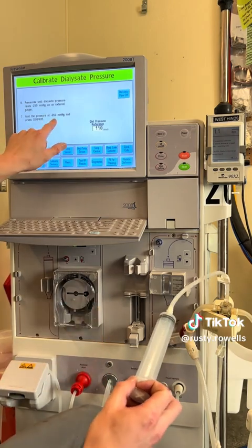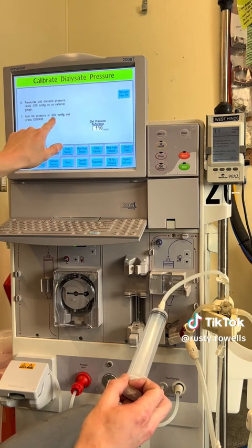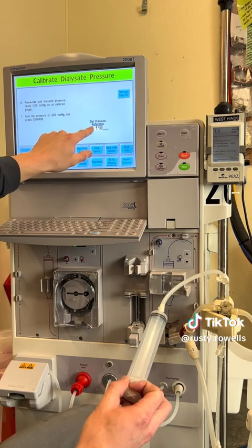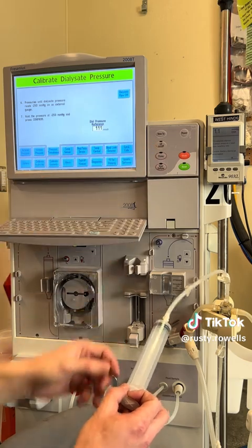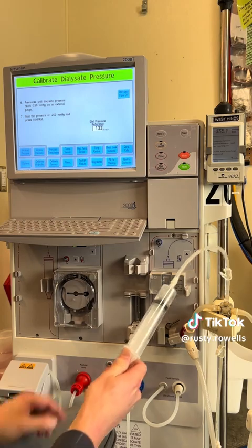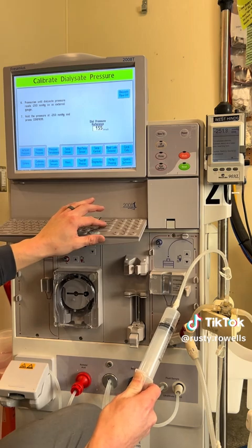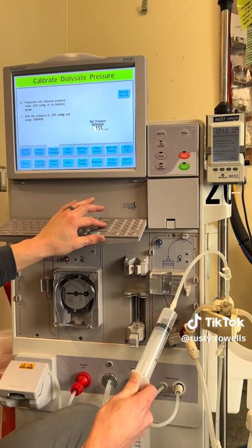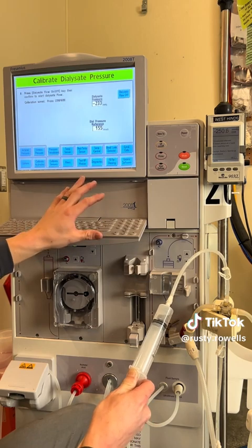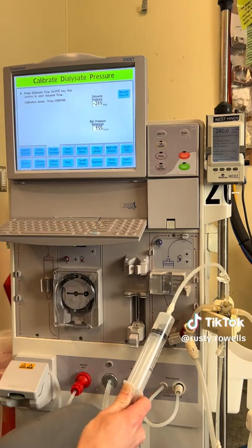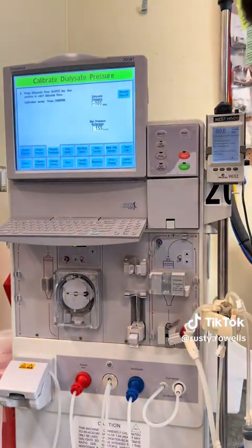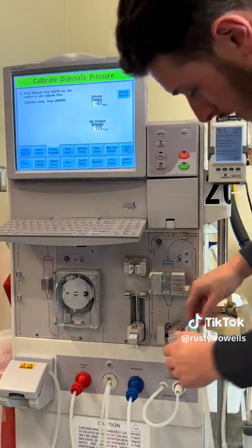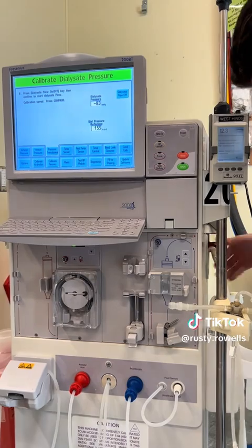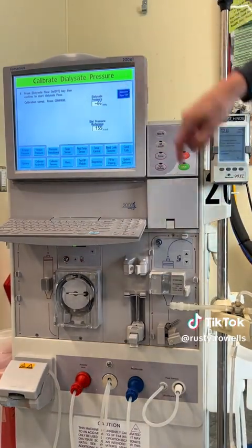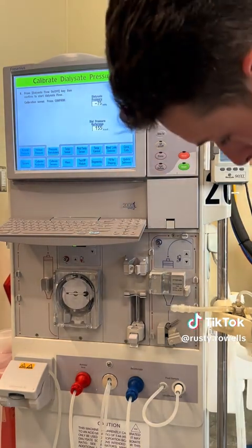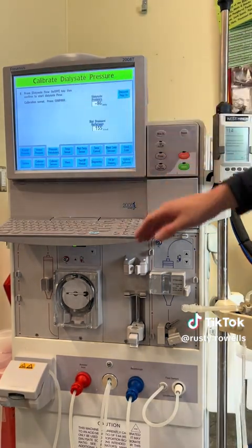Now we hit enter and we have to hold the pressure back at -250, and then hit enter to lock that in. So we're going to pull back to -250, get it on the meter right here. When we reach negative 250 on the meter, I'm just going to hit enter to lock it in. And we've accepted the calibration now. All you do now is lift your shunt door, take your lines off, and connect them back up to the shunt door. Close the door, turn your dialysate pressure back on. We've got our bob moving over here on the side, and then just hit enter.